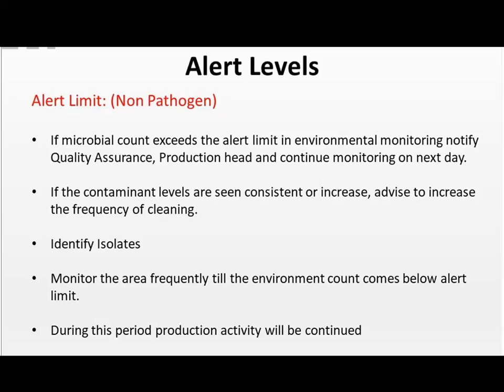You can also have in your procedures where 3 consecutive days of that alert level will qualify as an action level, and then you want to identify that bioburden that you're seeing. You want to see, again, if these are consistent, if they increase or if they decrease. And again, like I just said, identify the isolate. And the key is to monitor until it goes below that alert level.